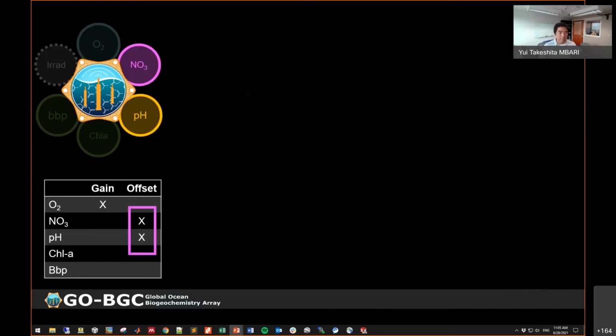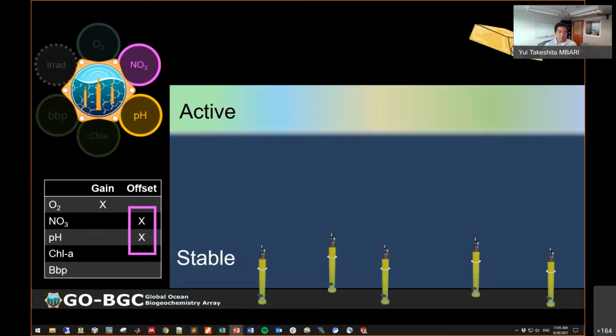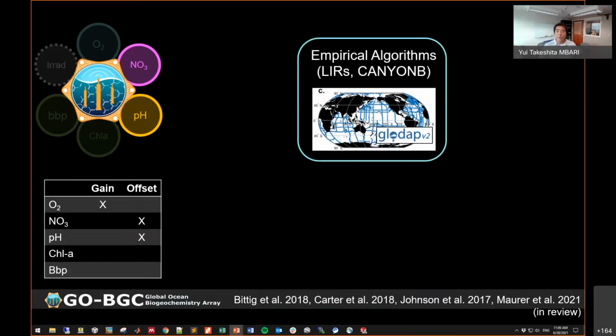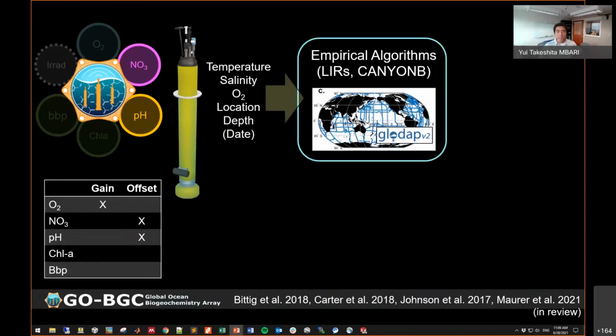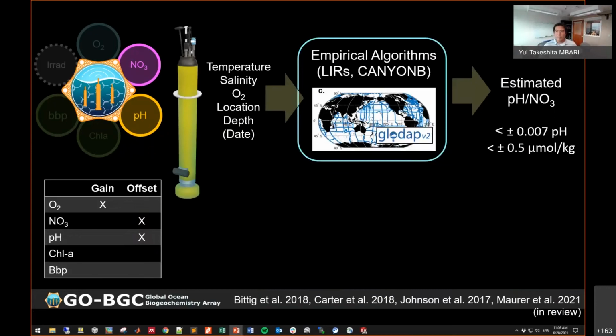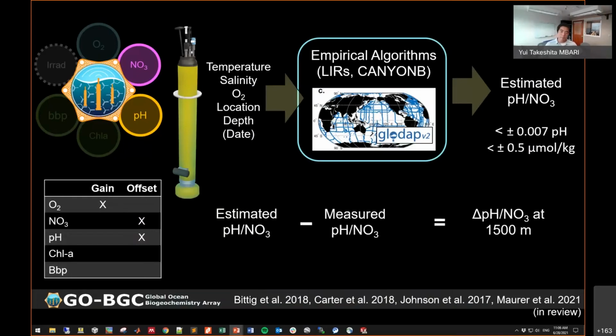Okay, so nitrate and pH. We adjust both of these sensors by applying an offset. For this, we use the deep measurements at 1,500 meters because the deep ocean is fairly stable and also predictable. If you have reference measurements in the deep ocean, then we can compare that against the sensor measurements and correct for drift. How we do that is to use empirical algorithms with the inputs of temperature, salinity, oxygen, location, depth, and date. The output is estimated pH or nitrate, with an accuracy of better than 0.007 for pH and half a micromole per kilogram for nitrate. Then we compare this estimated parameter to the measured parameters and calculate this anomaly. This anomaly is essentially the sensor drift at depth because we assume that the estimated values are accurate.